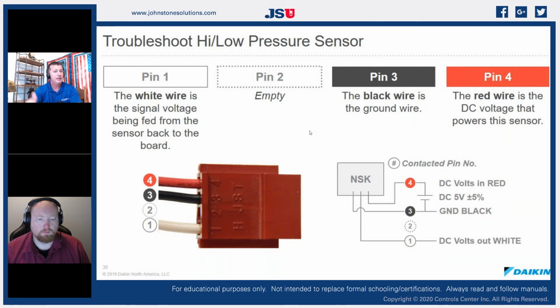So it's very easy to troubleshoot these inverters when we know how they're operating, right? So I can simply take my meter, put it on volts DC, and I can check from number 3 to number 4 to see what the voltage is going in to make sure I got 5 volts DC. And then I can check from ground to number 1 to see what my voltage is coming out. And then I can look at my chart and it will tell me what it is actually reading. A lot of thermostats, you can even walk over to the thermostat and go into the sensor status menus and look at these readings. You don't even have to put your gauges on them. You can go look at all of these temperature sensors and pressure transducers.